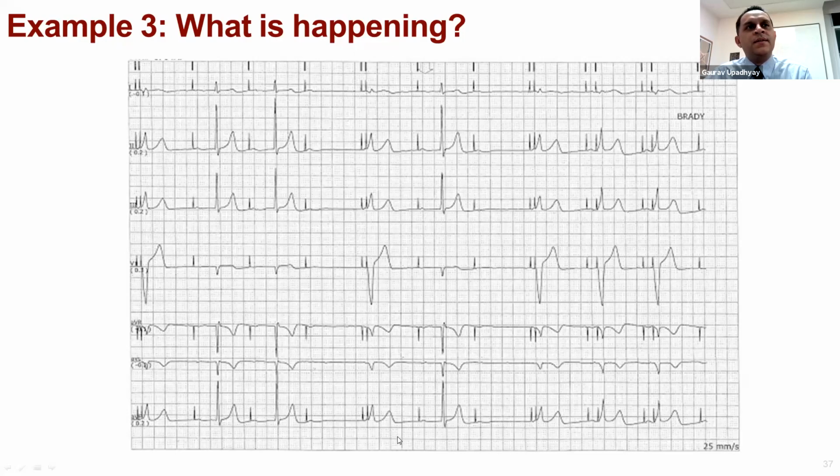So at the start of the telemetry feed, we've got atrial pacing. Then we have a ventricular pace beat, another series of atrial pace beats, and then it's switched. So the pacemaker here is changing mode. It's changing from pacing primarily in the atrium to pacing both the atrium and the ventricle. And what is characteristic of AAI to DDD, that transition in managed ventricular pacing, is that you have the allowance of a dropped beat.